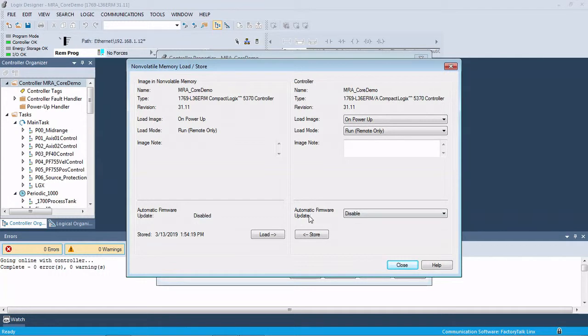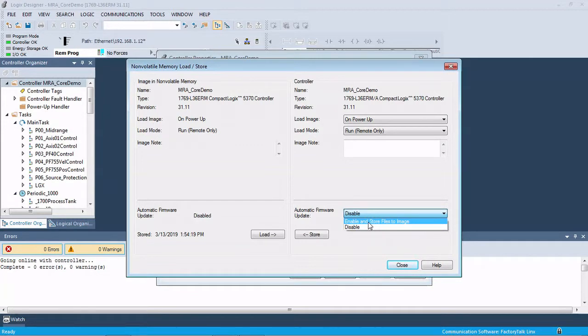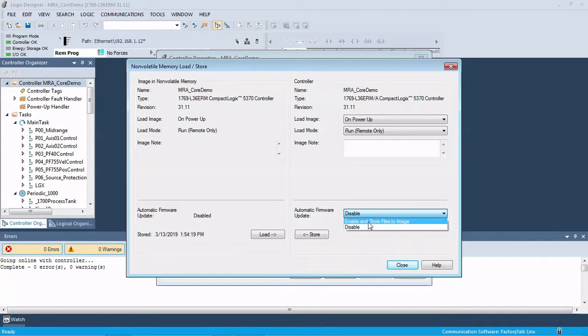The automatic firmware updates. What this is, if I click this over to enable, you would back up the firmware to any IO modules, drives, anything connected to this processor via network or the local chassis to the SD card. And then if they're set to an exact match in the firmware setup in the properties tab of that module, then they would have their firmware backed up. And then anytime you replace that module, it will again receive its firmware from the SD card. We're going to cover that in another video. So right now I'm just going to leave this at disable.